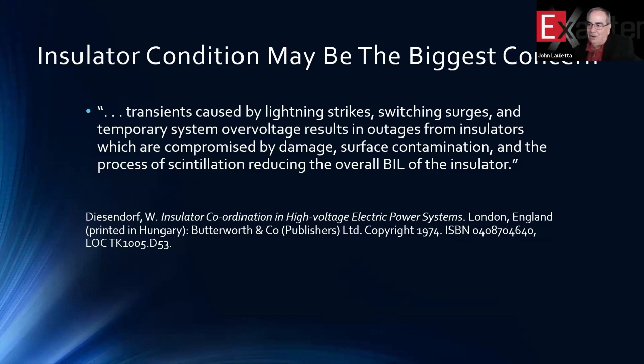This study was interesting just because it calls out the fact that contaminated insulators that are in this process of scintillation, so they're contaminated not just casually but actively, and are participating in the pole fire process, really are a problem for a number of reasons. Because now this insulator has been damaged in its ability to insulate the wire from the ground or from the pole. And it's like reducing its BIL, basically. And it's because these dry bands on the insulator itself are not as insulating as the normal glaze of the insulator itself. So the insulator, as it collects these dry bands, these little pockets of heated contamination, begins to deteriorate the function of the insulator itself.